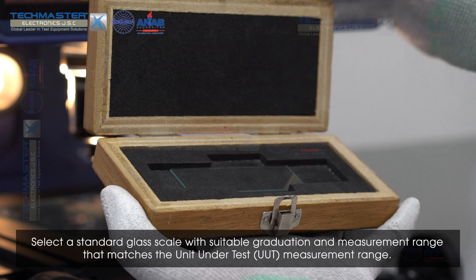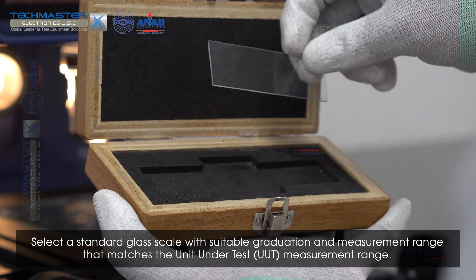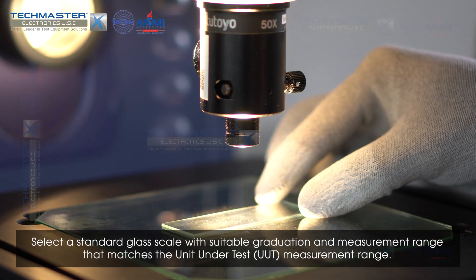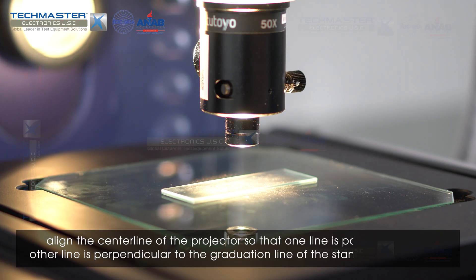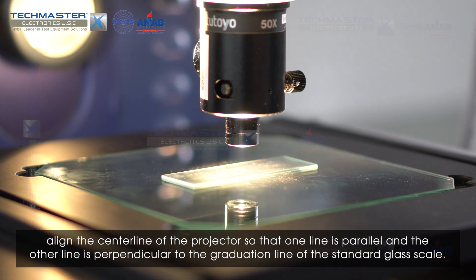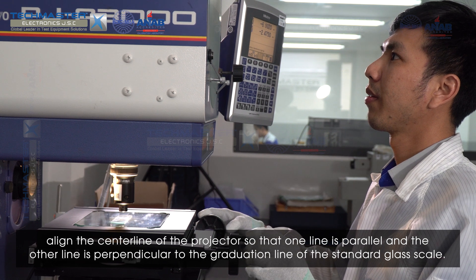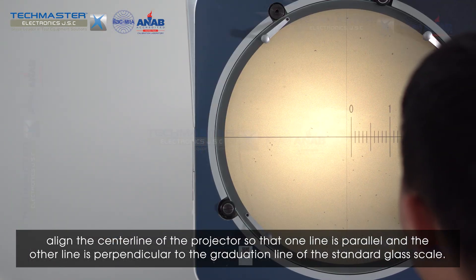Select a standard glass scale with suitable graduation and measurement range that matches the unit under test measurement range. Place the standard glass scale on the measuring table. Align the center line of the projector so that one line is parallel and the other line is perpendicular to the graduation line of the standard glass scale.